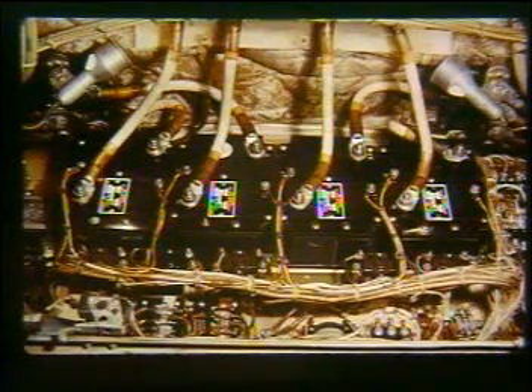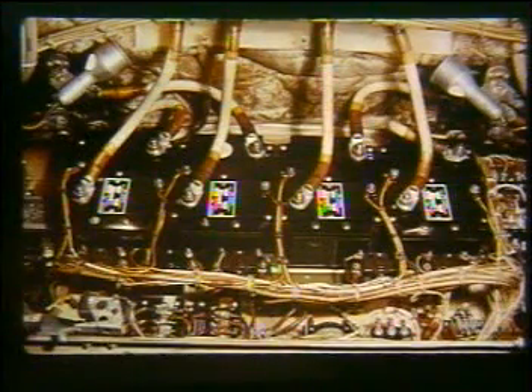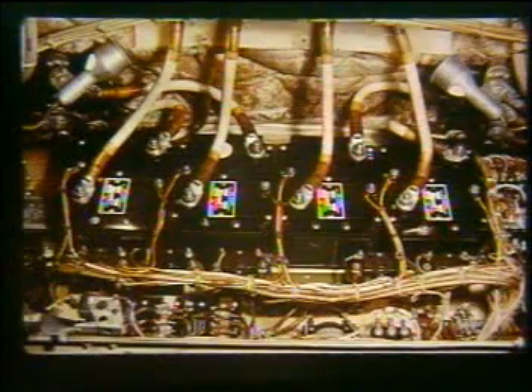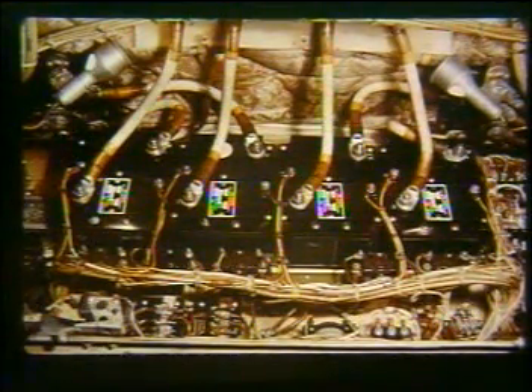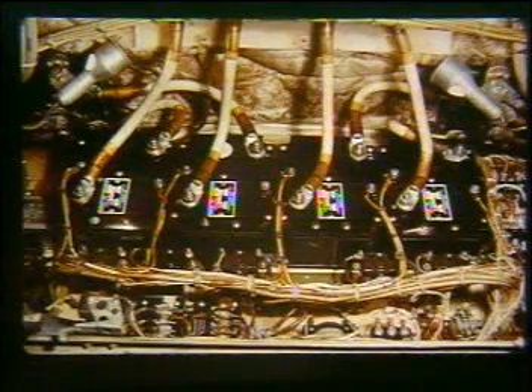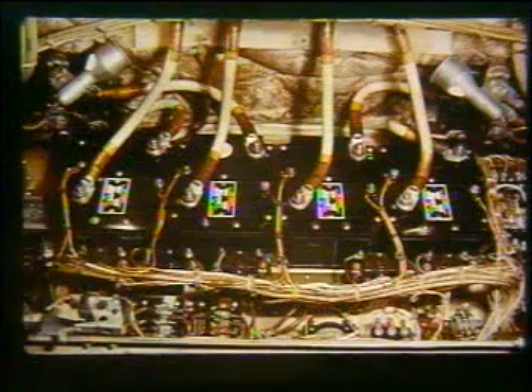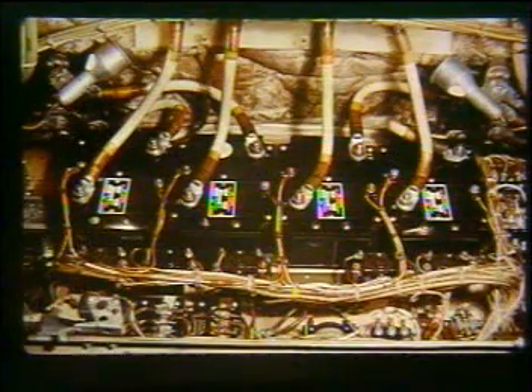The line switch relay operating with the generator switch on the generator control panel will connect or disconnect the generator output to the master bus. The reverse current circuit breaker provides protection for the master bus and the generator in the event of a generator failure, line switch relay failure, or a short in the generator feeder cable.